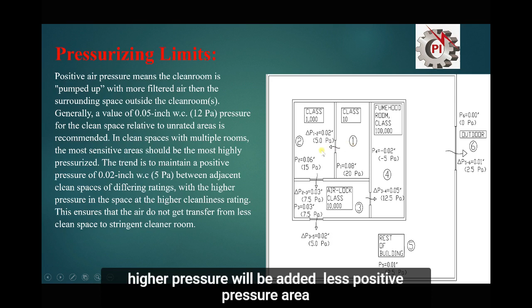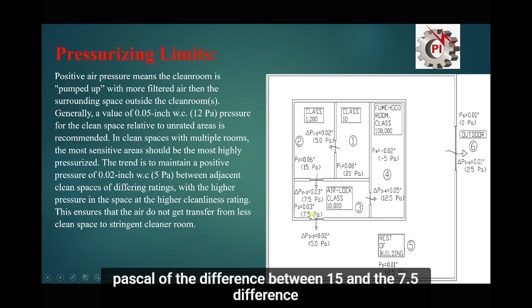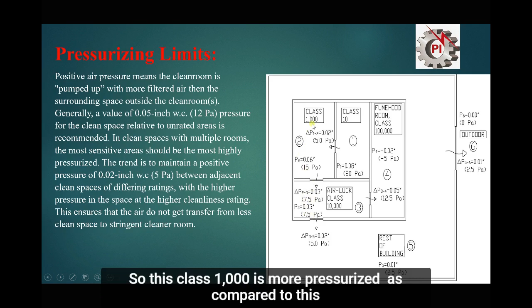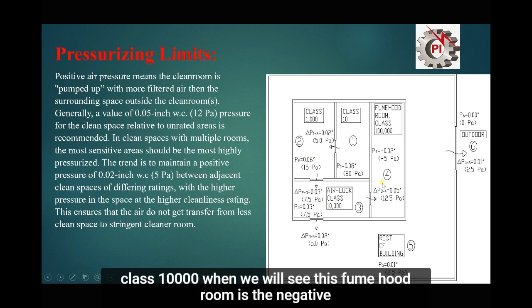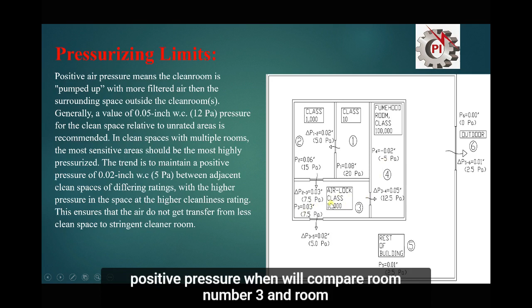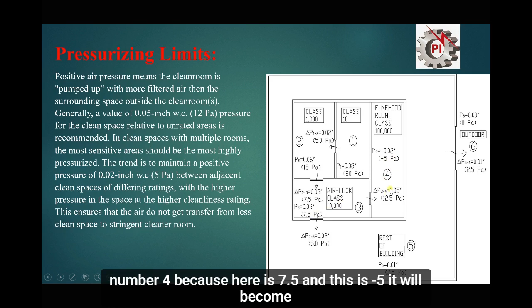Then we will see room number 3. In room number 2, the pressure is 15 Pascal, and in room number 3, the pressure is 7.5 Pascal. The difference between 15 and 7.5 is 7.5 Pascal. So this class 1000 is more pressurized as compared to this class 10,000. Then we will see this fume hood room. Here is the negative pressure, -5, and here was the positive pressure. So when we compare room number 3 and room number 4, because here it is 7.5 and this is -5, the difference becomes 12.5.